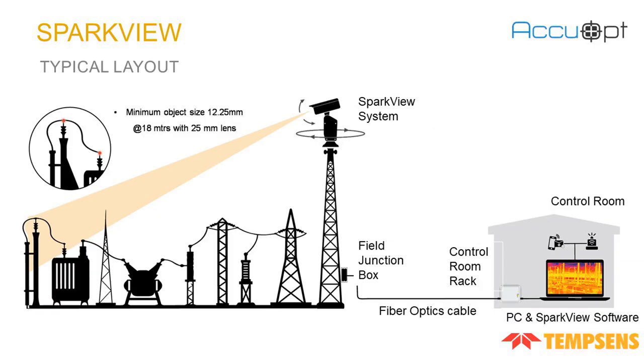This is the typical layout for the SparkView system. The SparkView will be installed at a 2 to 3 meter height from the monitoring component to have a clear line of sight. As you can see in the image, the hotspot is detected with minimum object size of 12.25 mm at 18 meters distance with a 25 mm lens. This is a 384 resolution camera.